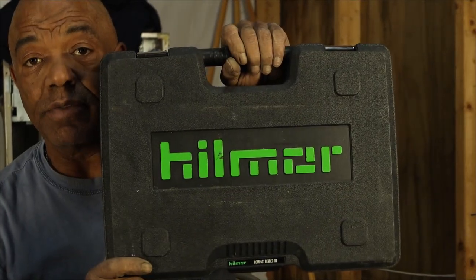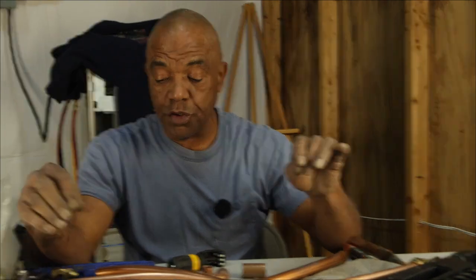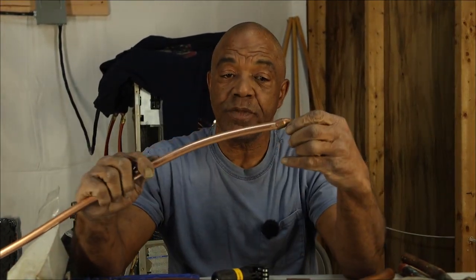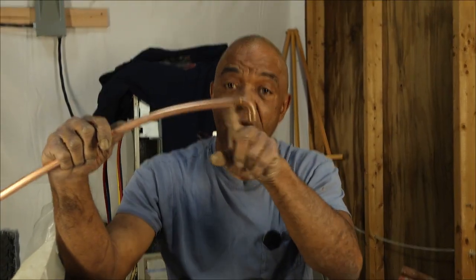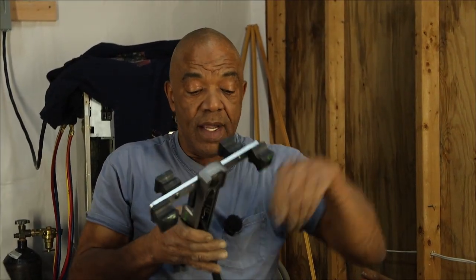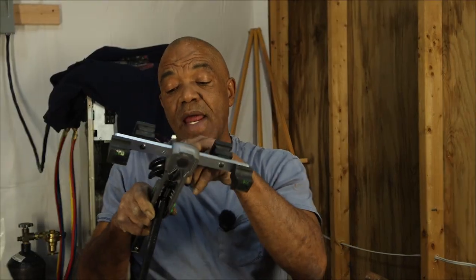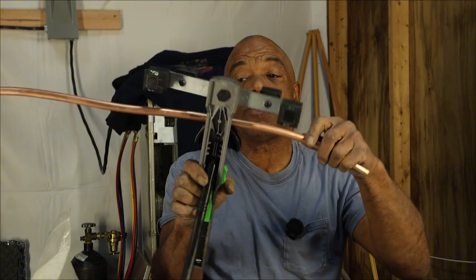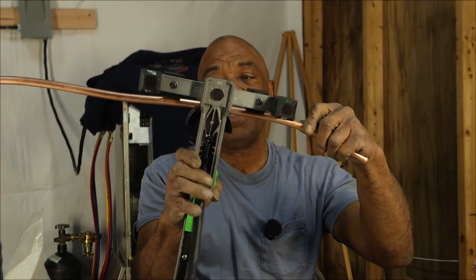my tubing bender. Showed you this earlier, but let's really understand the convenience of why you would want to use a tubing bender as opposed to using an elbow, okay? When I use the elbow, like I said, I got two connections.